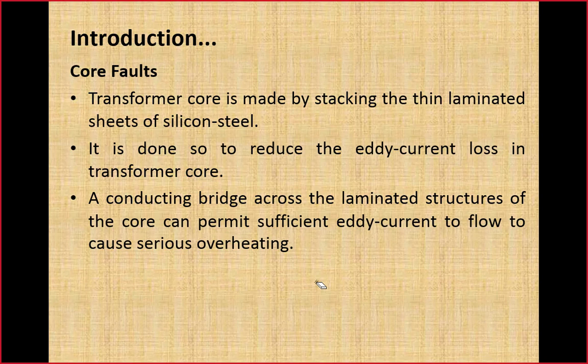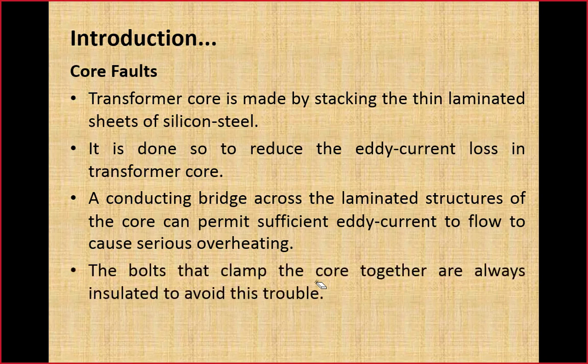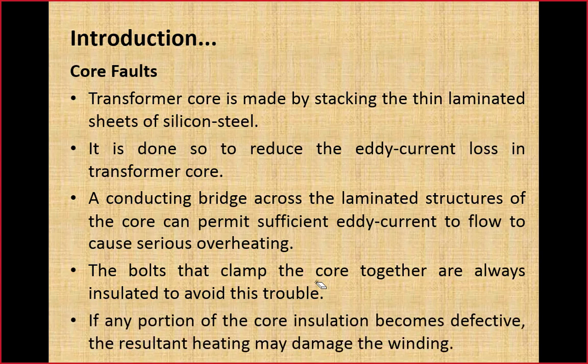So there could be a path for the flow of eddy currents, and that may result in higher I square R losses within the core due to eddy current. The bolts that clamp the core together are always insulated to avoid this trouble. If any portion of core insulation becomes defective, the resultant heating may damage the winding, because the core temperature will increase, the transformer internal temperature will increase, and that will damage the insulation of the winding.